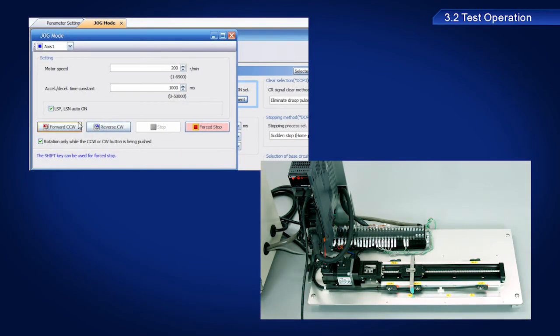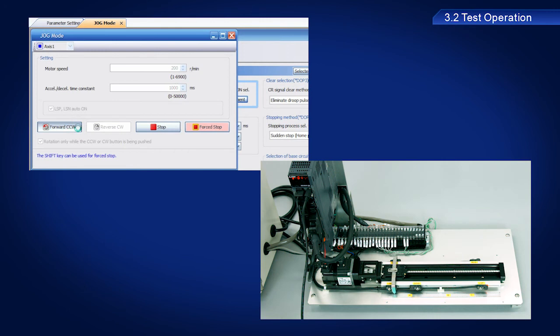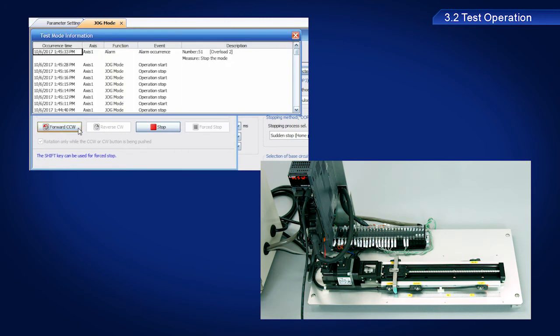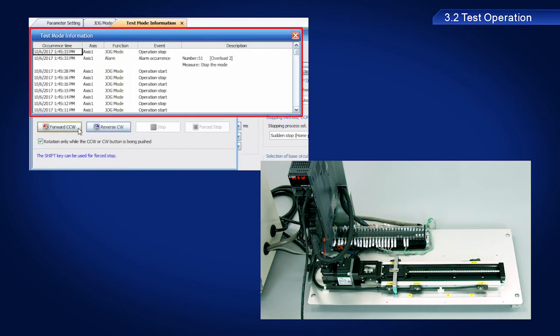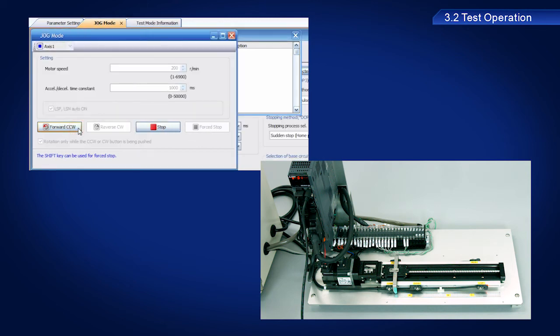If the LSP or LSN limit is exceeded during this time, the servo amplifier will stop and alarm display appears. Once the servo amplifier stops, clicking the forward CCW and reverse CW buttons will have no effect.